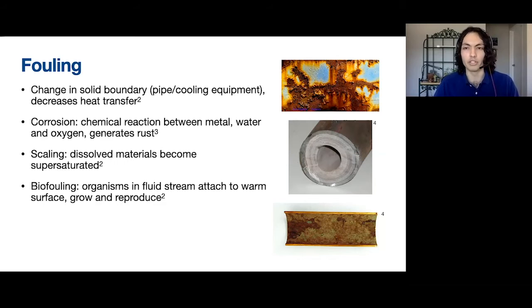In our case of the cooling system, the water coming in from the water line has some dissolved materials, and maybe they're dissolved when it comes in, but solubility changes with temperature. So at the different temperatures within the cooling system, those salts might not stay dissolved. They become supersaturated and can form large deposits like the ones shown in the middle picture.